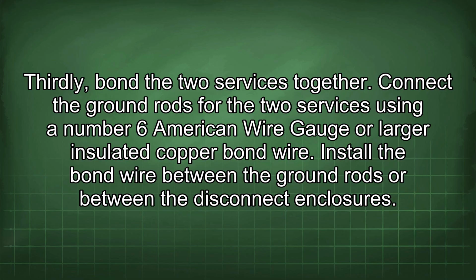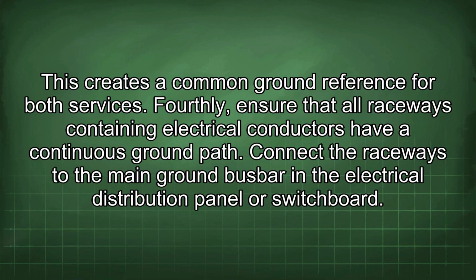Thirdly, bond the two services together. Connect the ground rods for the two services using a number 6 American wire gauge or larger insulated copper bond wire. Install the bond wire between the ground rods or between the disconnect enclosures. This creates a common ground reference for both services.